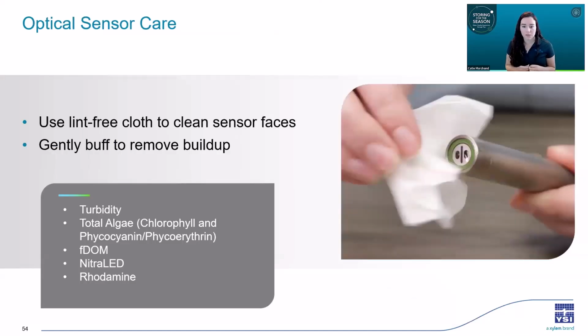Next, optical sensors are also easy to care for. These are like turbidity, chlorophyll, DOM, dissolved organic matter, UV nitrate, and rhodamine. All you need to do is use a lint-free cloth to wipe the sensor faces clean. And for this, it's really important that it's a lint-free cloth like a Kim wipe, because any fibers from a paper towel can fluoresce, and that can interfere with your readings. Also be careful not to scratch the sensor windows, especially if they're made of glass. They can be more fragile.